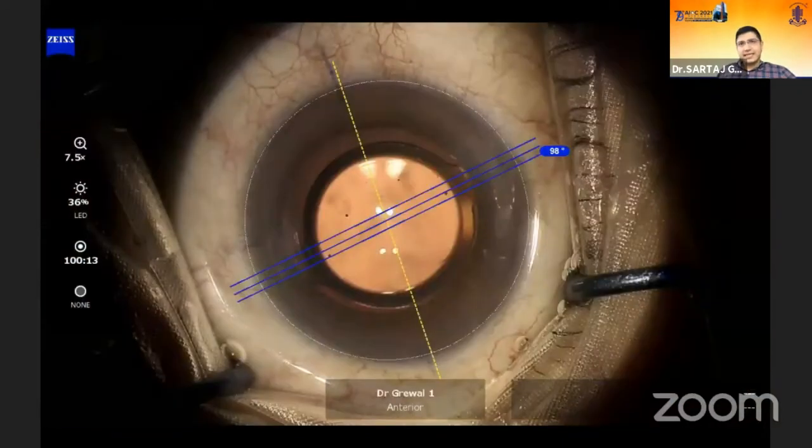Another reason is that aligning the lens with the large calipers is also easier on the screen, and also the accuracy of the Callisto software itself seems to be better than what it was in the previous generations, possibly because of the high resolution cameras that are being used.